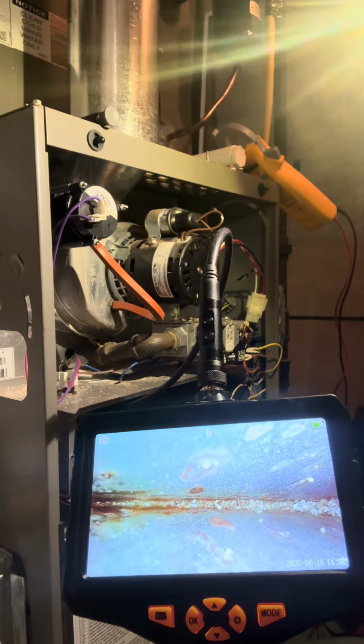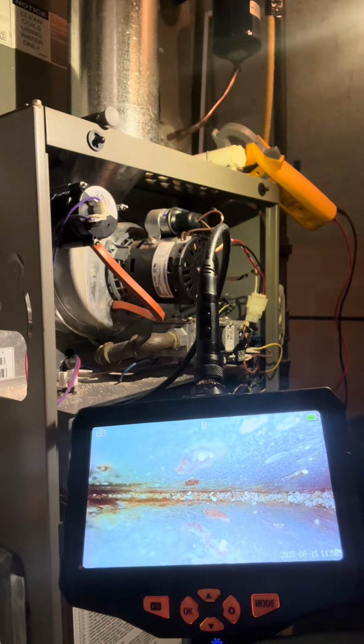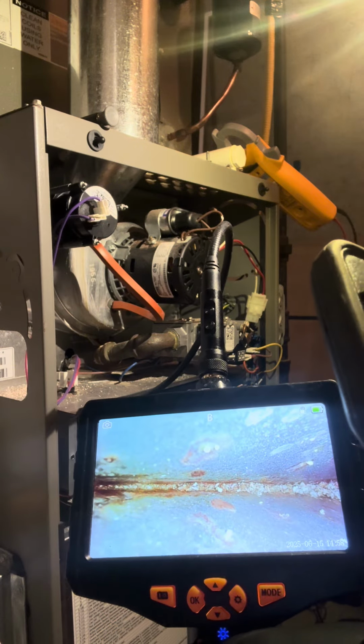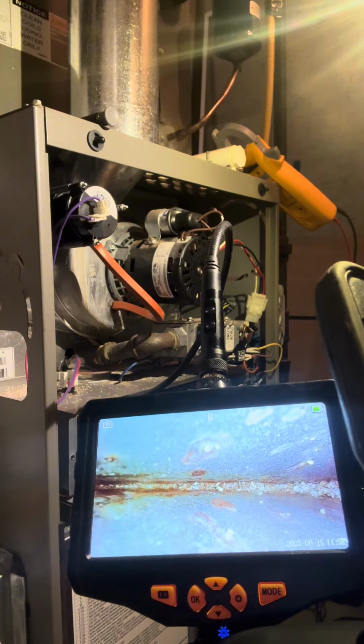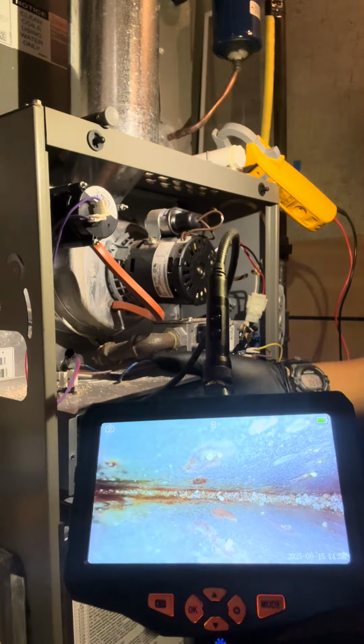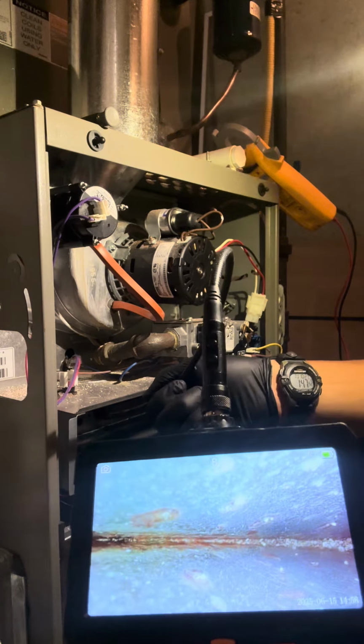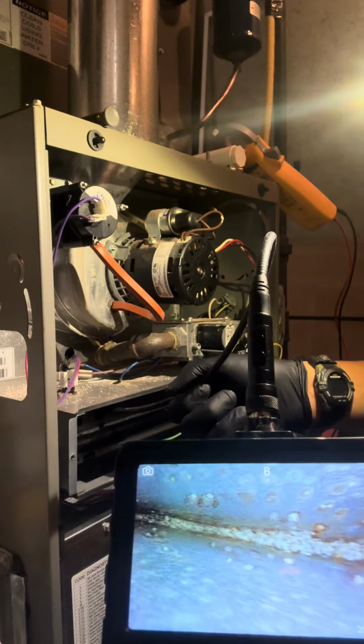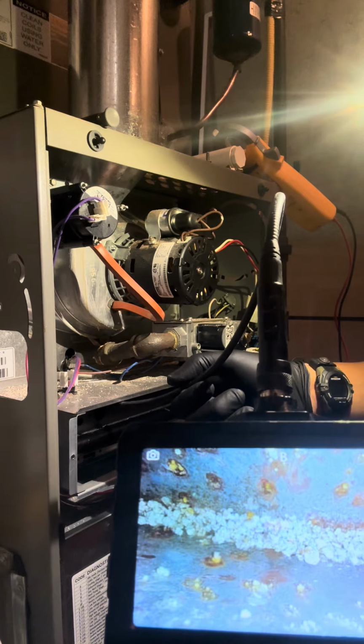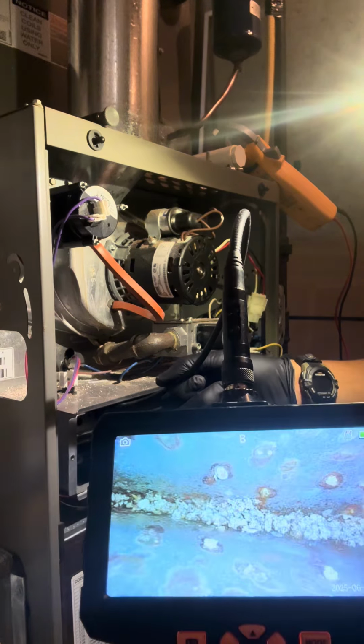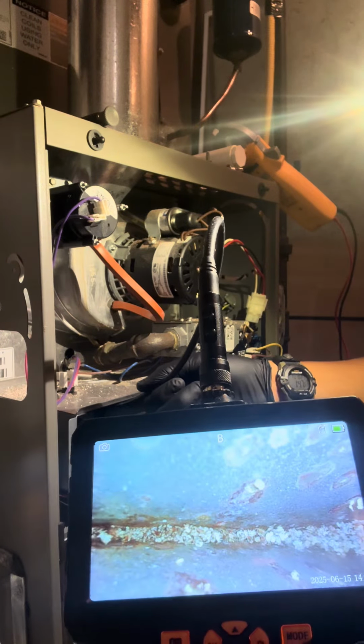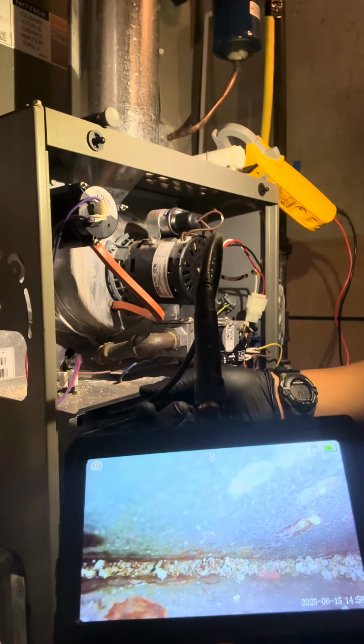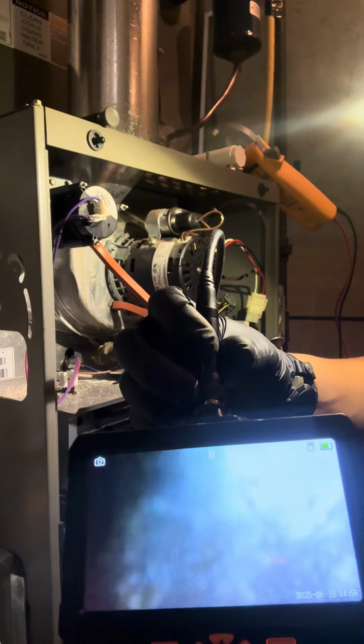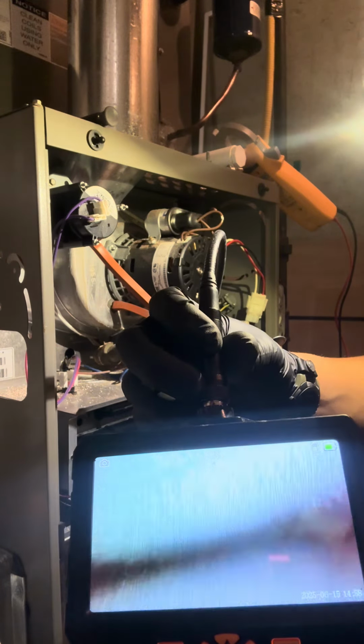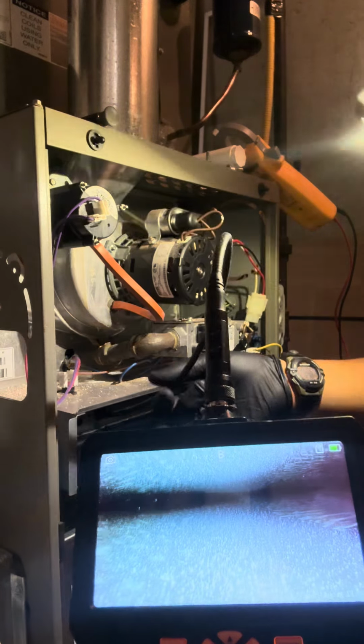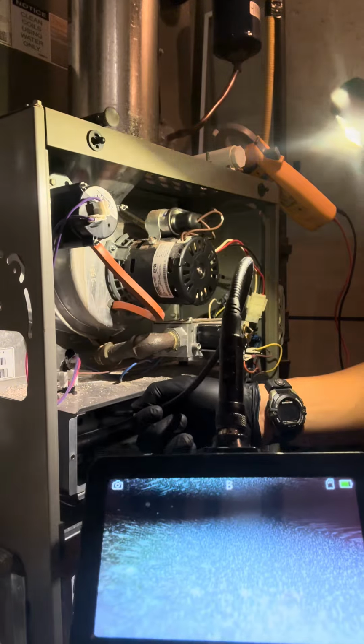When these heat exchangers come fresh out of the box, they are galvanized steel. So they're coated with a nice shiny material. But anytime you have flame and moisture and the byproducts of combustion, it will start to corrode and eventually it will crack. So that is what I'm checking for, because I want to make sure that there are no cracks in this heat exchanger.